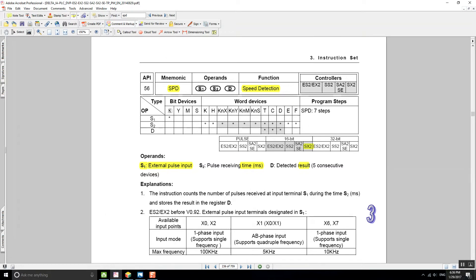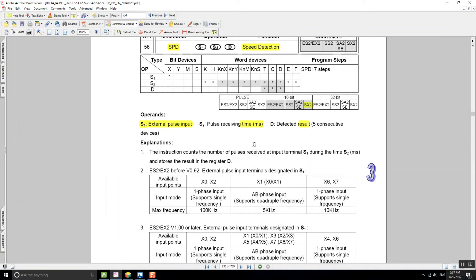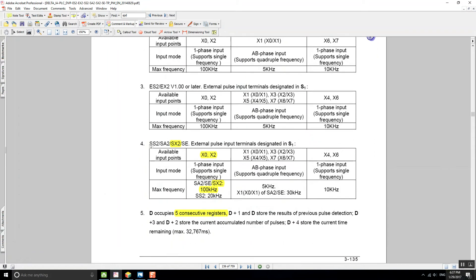S1 should be one of the PLC's high-speed inputs. For my model, I'm using the SX2, and for the SX2 the high-speed inputs are X0 and X2. Those are one-phase inputs and for those two inputs we can go up to 100 kilohertz.